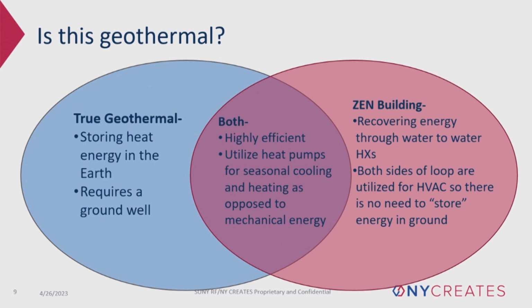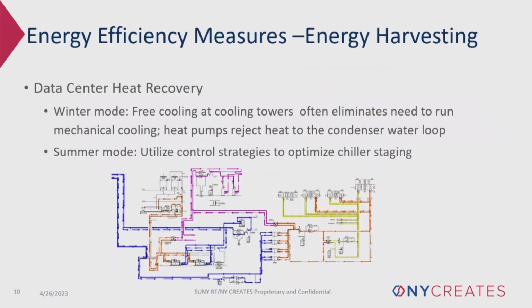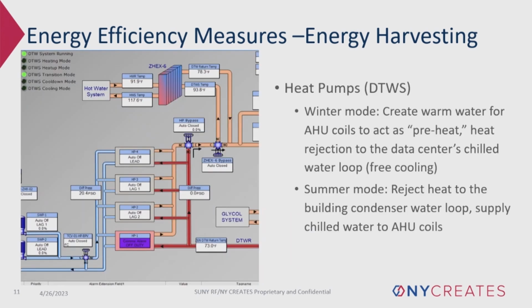As I said on one of my first slides, a unique aspect of this building is the Tier 3 data center, and that's what makes this possible because it's a constant cooling load regardless of season. Of all those loops, I'd like to discuss 3 critical ones today, starting with the data center. In the winter mode, we're able to harness free cooling by not necessarily running the chillers and simply running the cooling towers. And that also gives our heat pumps a way to charge themselves so that we can heat the building off of the heat pumps. These energy efficient chillers with variable speed drives also allow us to optimize summer operation as well.